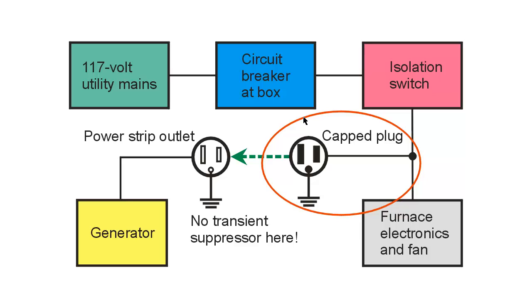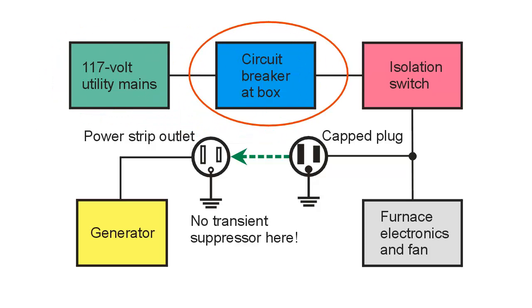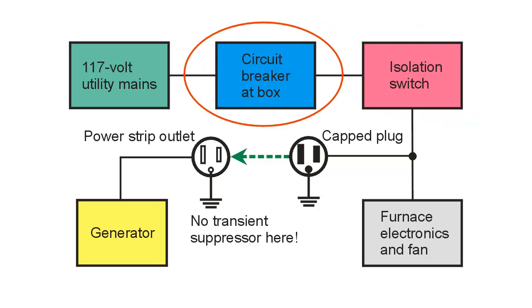When the power fails, there won't be any electricity to this circuit breaker box. Nevertheless, I open up the breaker that goes to the furnace electronics first — before I do anything else. After that, I go down to the furnace and open up the isolation switch, so we've got two layers of protection for external personnel and two layers of protection against contact in the event the power comes back on unexpectedly. You want this isolation switch and the open circuit breaker — that offers two layers of protection.